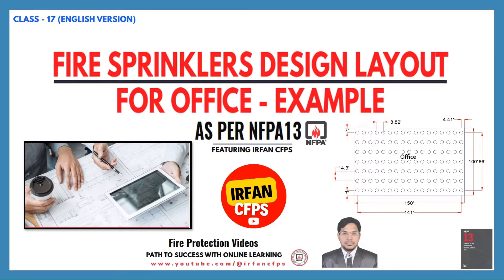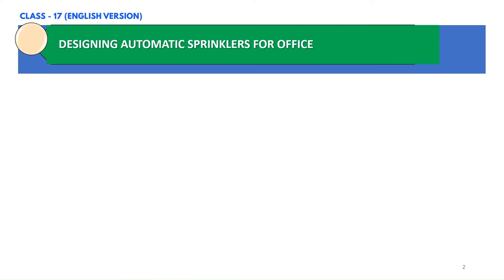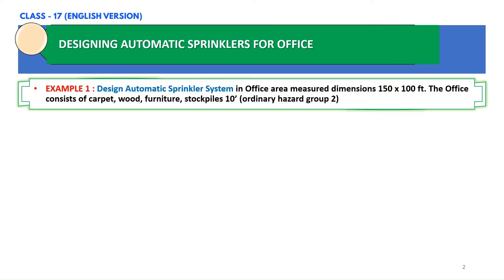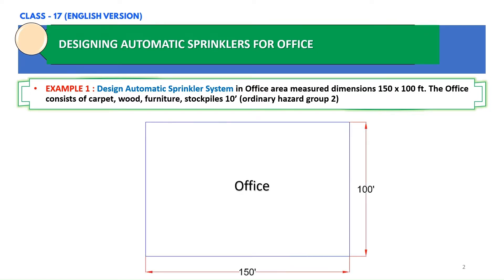Let us design automatic sprinklers in an office area by considering an example. We shall consider an office which has an area of 15,000 square feet with dimensions 150 by 100 feet. The example states that it consists of carpet, wood, and furniture with stockpiles about 10 feet in height. The occupancy is mentioned as ordinary hazard group 2. If you want to learn about the hazard occupancies, you can watch my video series on NFPA 13. The link can be found in the description box.